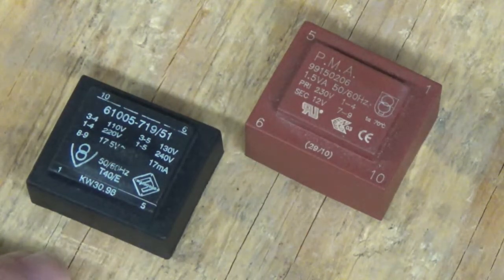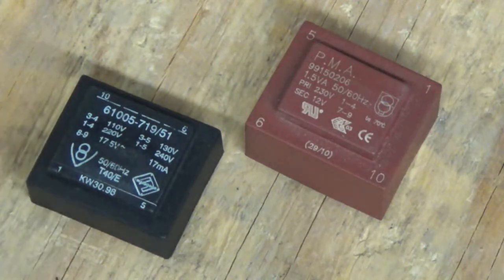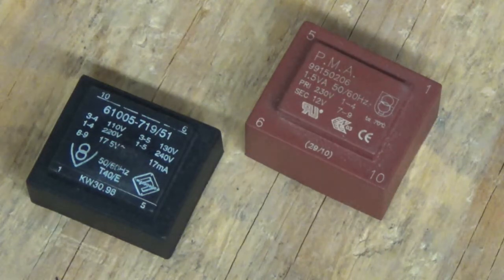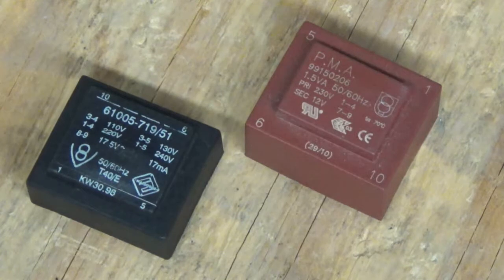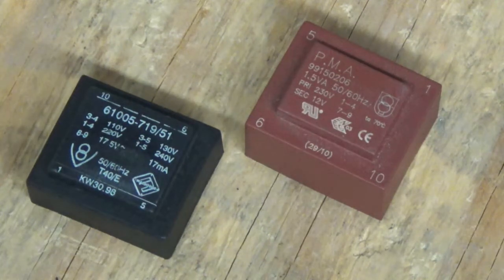And they have given up the ghost. Now usually when transformers fail, they'll fail on the primary winding side, where the line from the power plant comes into the transformer. Sometimes they give up the ghost from lightning strikes, surges in line voltage, or they just die from old age. These things work hard day in and day out, sometimes 7 days a week, 24 hours a day, 365 days a year for decades before they die of old age. They get stressed out pretty hard sometimes.